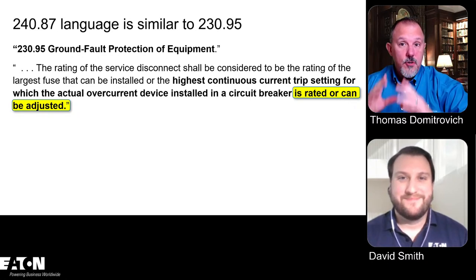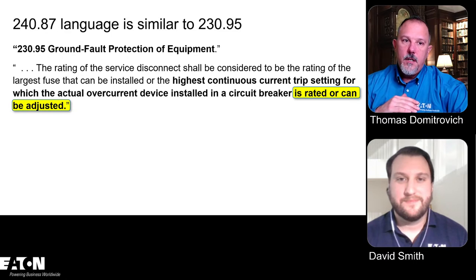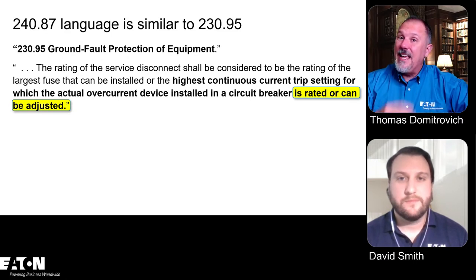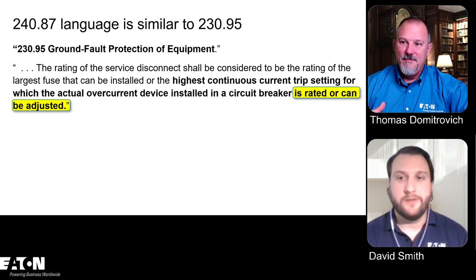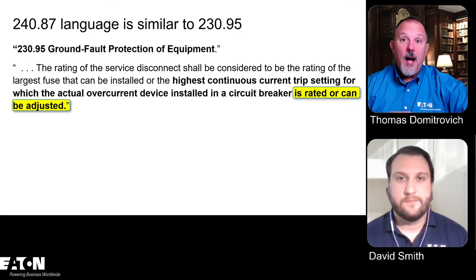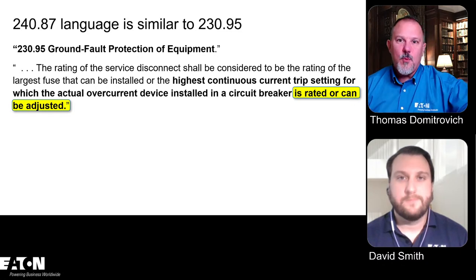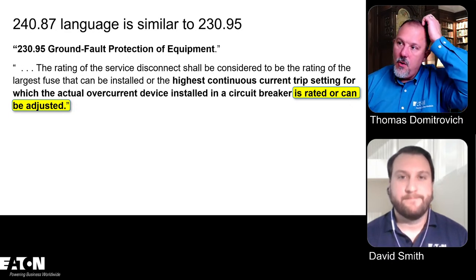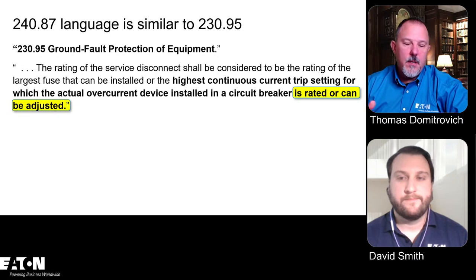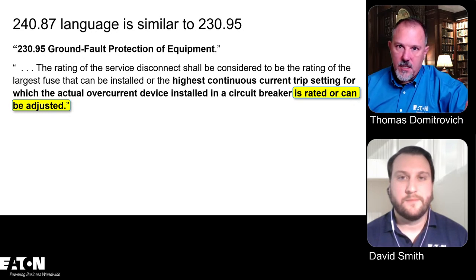And I said, so the solution, and the only way that I could, because remember in the second draft, you can't introduce anything new. No new material. So my options in 240.87, or our options as a panel, were very limited because we couldn't just scrap and say, oh, this is what we meant, because it would have been new material. So I built off of a public input that mentioned an ampere value. I threw out 1,000 amps in the second draft. I said, look, make it the same as ground fault protection of equipment, 1,000 amps and above.